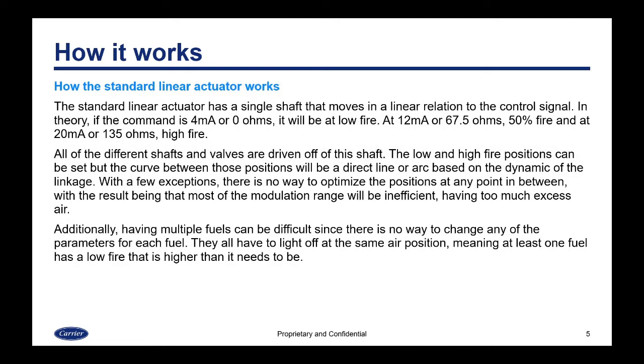So how does the standard linear actuator work? The standard linear actuator has a single shaft that moves in a linear relation to the control signal. In theory, if the command is 4 milliamps or 0 ohms, it will be at low fire. 12 milliamps or 67.5 ohms, it would be 50%. And at 20 milliamps or 135 ohms, it would be at high fire. All the different dampers and valves are driven off of this shaft.